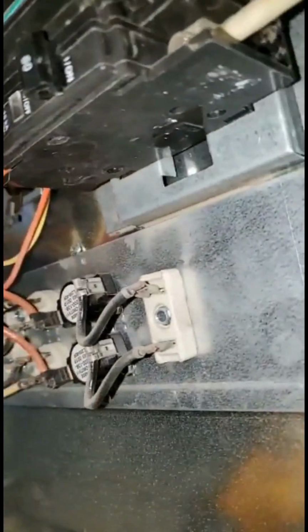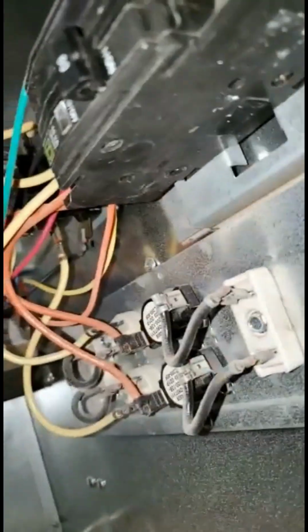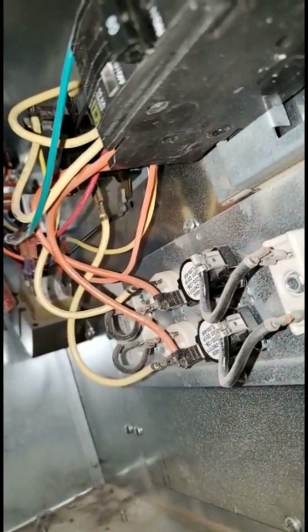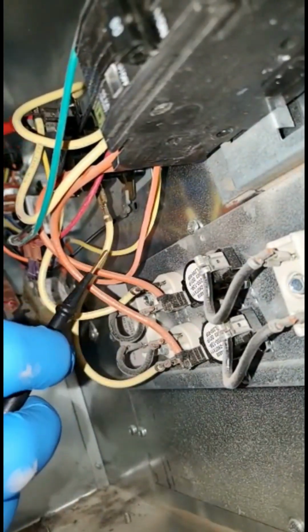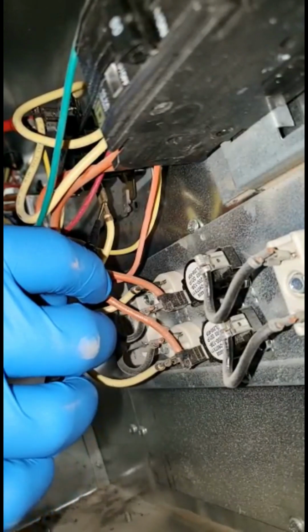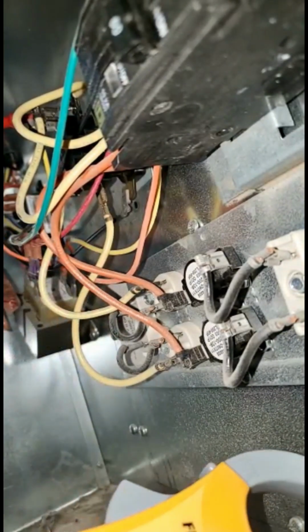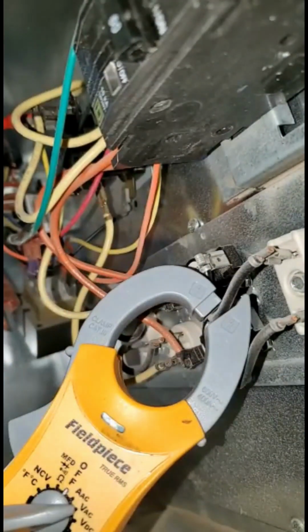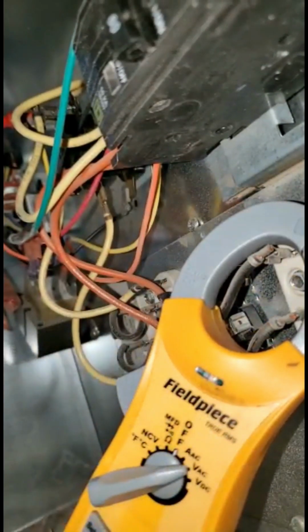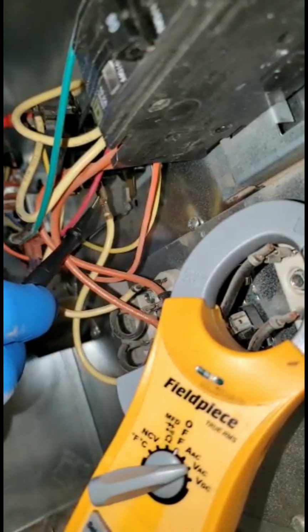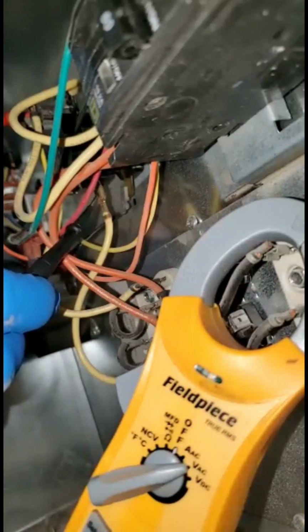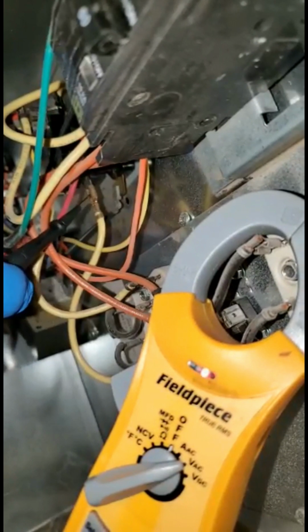And if I take a check, oops, so here, take a check right here, I'm getting a reading of, I can't quite get it in the shot. But it's reading 240 volts. So that means that it's not engaging all the way across there. So we've got a bad sequencer.